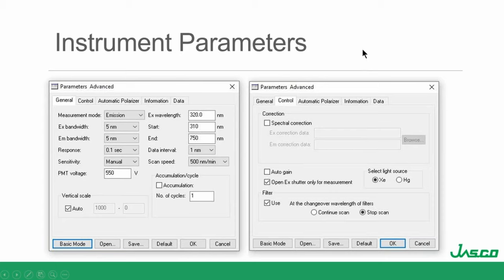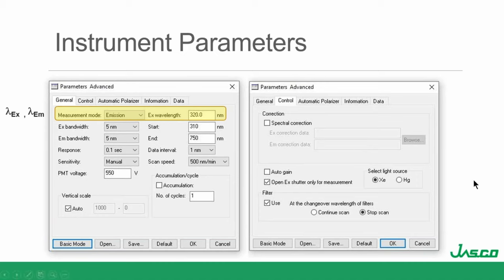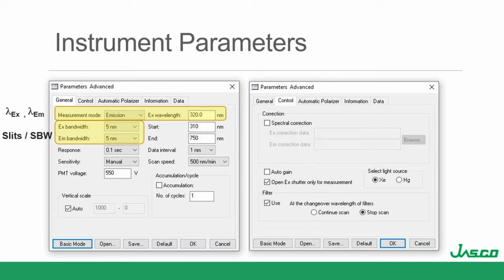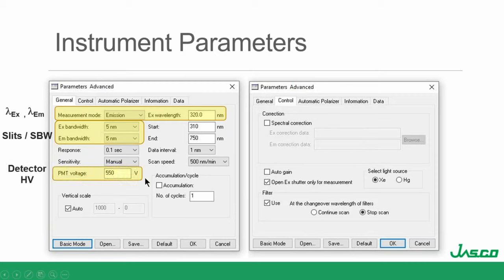Now that we know where the fluorophore is, what else can we do to optimize the signal? Right now we have huge scatter bands and a very small fluorescent band. This is a screenshot from the JASCO FP-8000 series software. We can adjust excitation and emission wavelengths, select the mode — whether excitation or emission scans — and equally or more importantly, excitation and emission bandwidth: how much light we let into each monochromator. This is critical and I don't think enough people adjust this. You need to determine what resolution you need as well as what sensitivity — and that means changing the detector voltage.